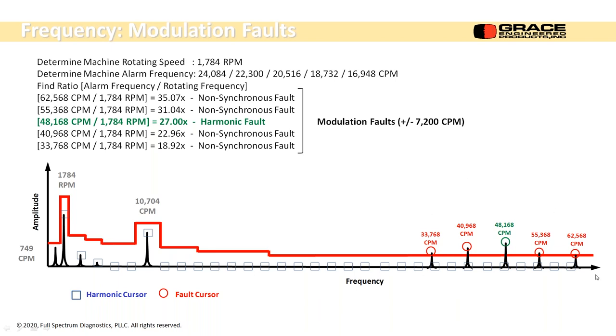That's how some rolling element bearings fail. They'll modulate at 1 times RPM. This is modulating at an electrical frequency. This is 120 hertz, or you multiply it by 60, it's 7,200 CPM, telling me that there's a rotor bar pass problem in my motor, okay? You don't really need to diagnose it to that extent. I'm just trying to give you an idea that there's a center frequency and there's a spacing on the sidebands, and the spacing's telling you the source, and how it's modulating. So that's one type of modulation fault.